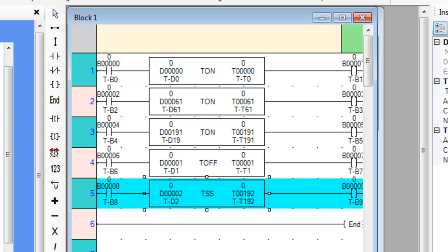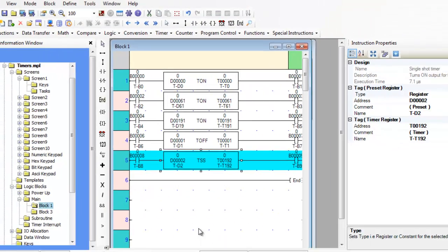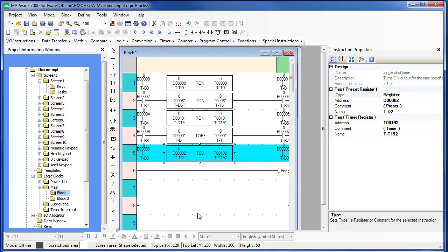Since the single shot timer only requires a pulse to turn it on, input contact B8 does not have to remain on during the entire count. Output B9 will turn on during the count and remain on until the count is reached. Notice that we never use the same timer address twice. Once you have associated a particular timer address with a timer instruction, you cannot use it again for another timer.